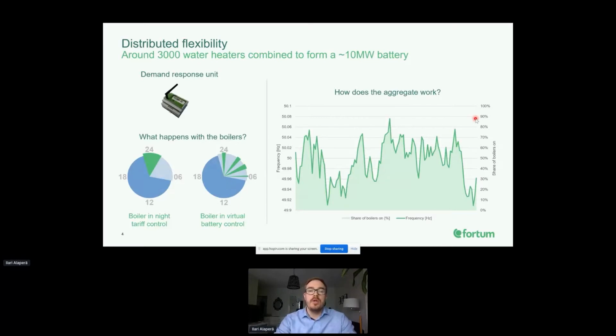We offer frequency containment reserve services from it. If the frequency goes high, we turn more boilers on, storing the excess electricity in the grid in these residential boilers. If the grid frequency goes down, we turn off the boilers, reducing the loading on the grid caused by them.